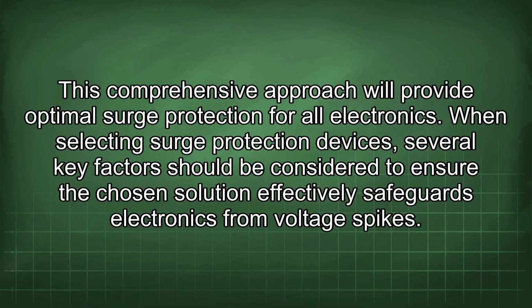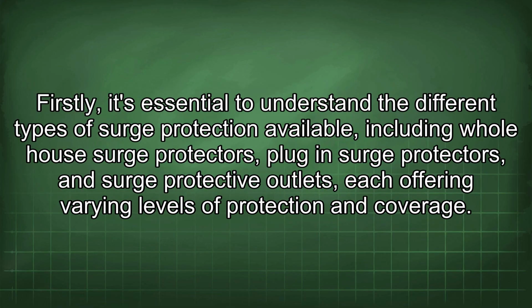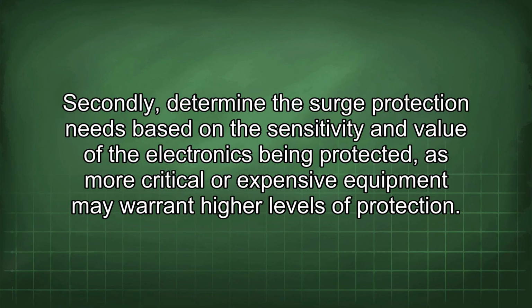When selecting surge protection devices, several key factors should be considered to ensure the chosen solution effectively safeguards electronics from voltage spikes. Firstly, it's essential to understand the different types of surge protection available, including whole house surge protectors, plug-in surge protectors, and surge protective outlets, each offering varying levels of protection and coverage. Secondly, determine the surge protection needs based on the sensitivity and value of the electronics being protected, as more critical or expensive equipment may warrant higher levels of protection.